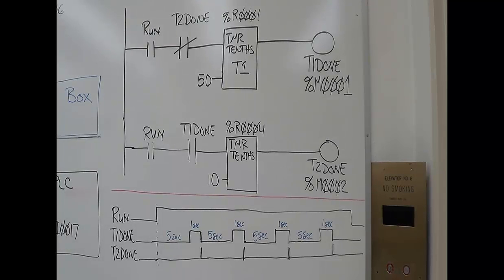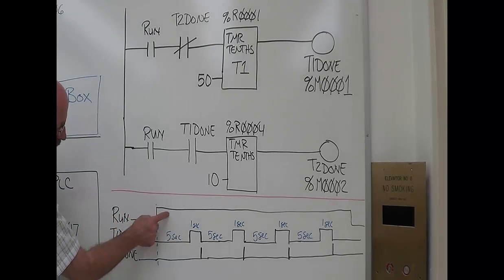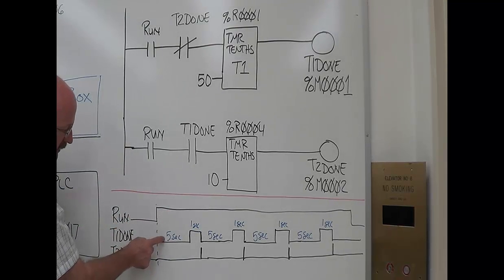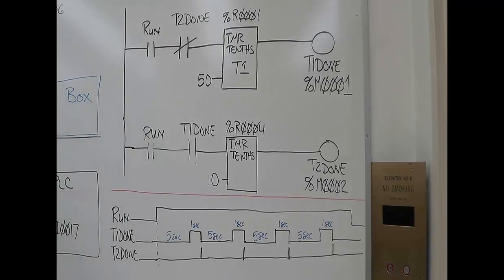So let's say, for instance, I need a valve to operate for 5 seconds and then a valve to operate for 1 second. First valve is 5 seconds. So I look at my timing diagram. As long as run is on and T1 done is off, that's my 5-second valve output.